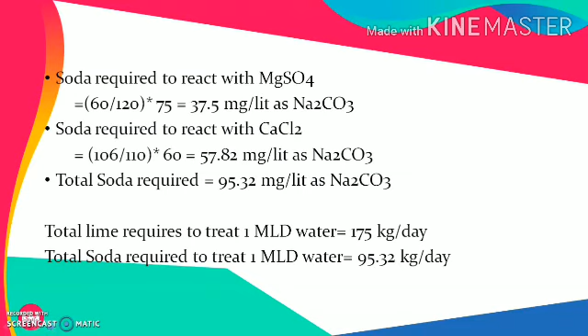Once we estimate the total amount of soda and lime required, we can calculate the total lime and soda required to treat 1 million liters of water. Using these formulas and this estimation, we conclude that the total lime required to treat 1 million liters of water comes out to be 175 kg per day, while the total soda required is 95.32 kg per day. This is very useful in deciding the operation and maintenance of the plant used for reduction of the hardness.